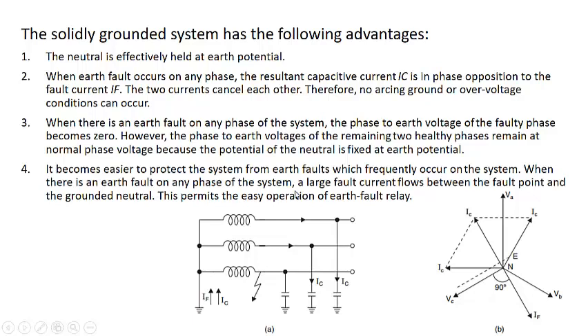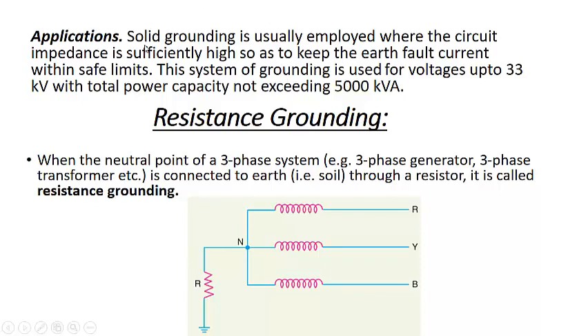When there is an earth fault, a large fault current flows between the fault point and the ground system. This permits an easy operation of the earth fault relay, and we can say detection and isolation of the system. This faulty part of the system can be isolated. Now this is applicable usually where the circuit impedance is sufficiently large, so the earth fault current is kept within safe limits. This system of grounding is used for voltages up to 33 kV with a total power capacity not exceeding 5000 kVA or 5 MVA.